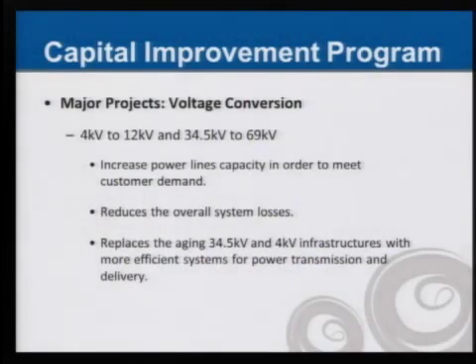The next major project is our voltage conversion project, which converts our distribution voltages from 4 kV to 12 kV and our subtransmission voltages from 34.5 kV to 69 kV. This will give us a lot more capacity on our lines to help meet customer demand, and by increasing the voltage, it will decrease losses on our system. In addition, we're replacing older infrastructure with new, more efficient equipment.